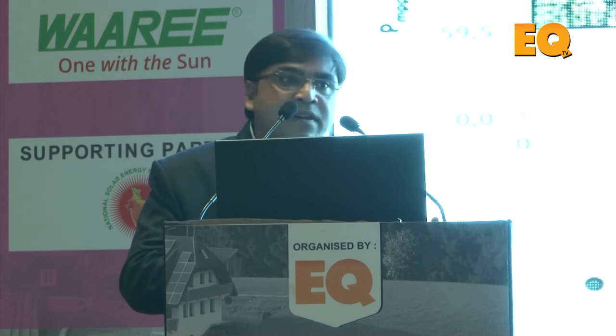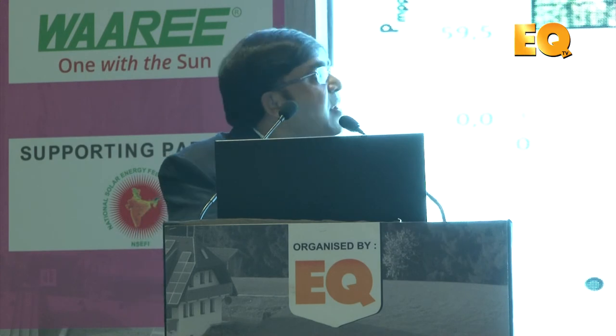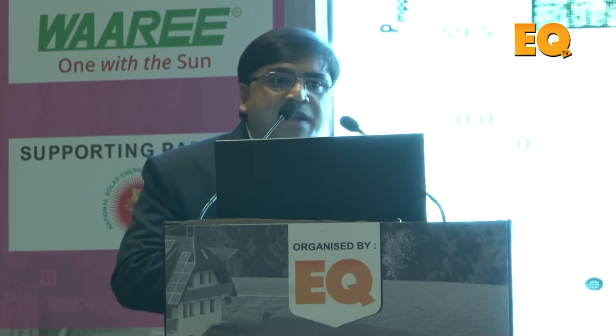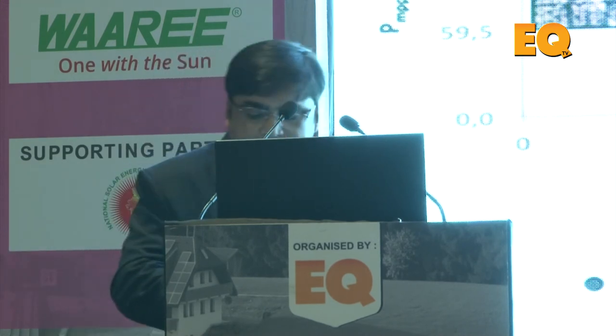Another phenomenon is the PID. PID is a shunting. And why is it happening? Because the sodium ion is coming, and that is making the shunting. And it has been found that this acetic acid is really helping the sodium ion to move from the glass to the solar cells, and that's really accelerating it. So if you can avoid this kind of thing. People are spending money on the solar cells, they are putting capex into some kind of technology, they are putting in the oxide layer, they are modifying the silicon nitride.